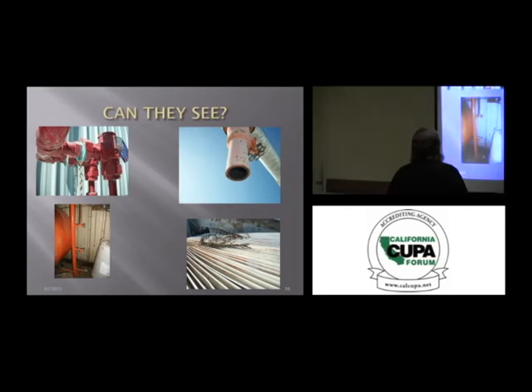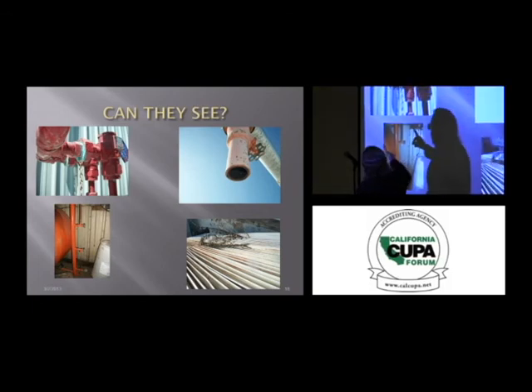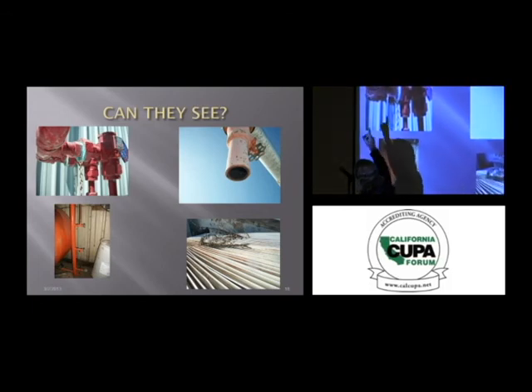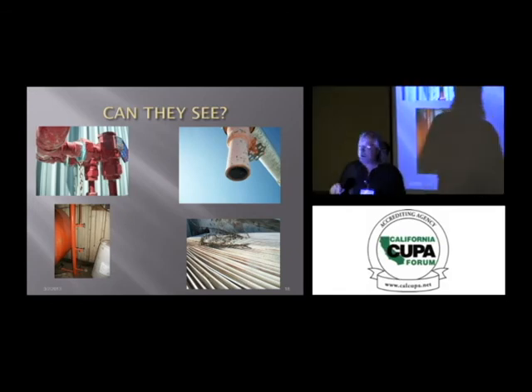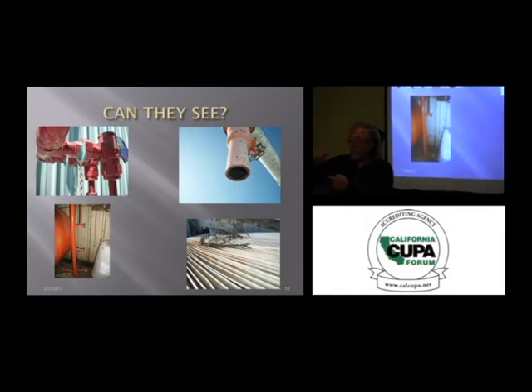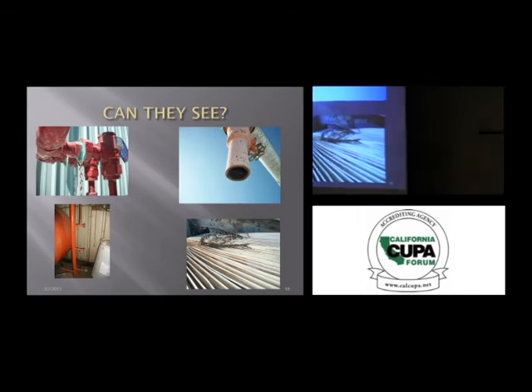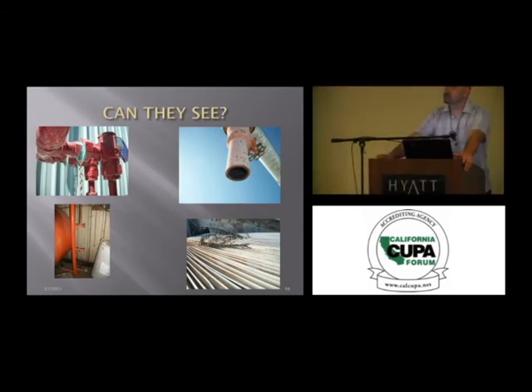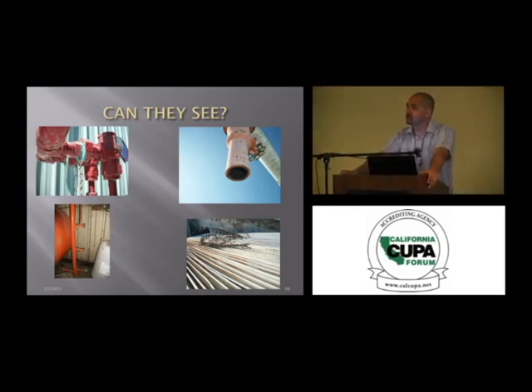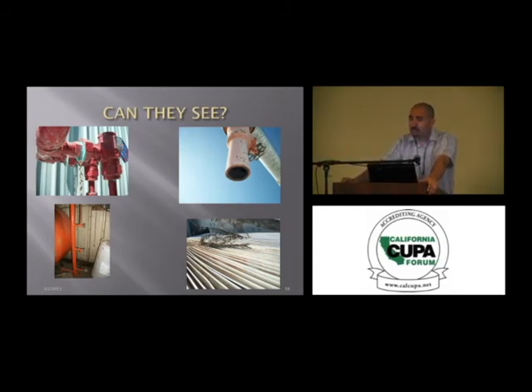What we like to do when we install relief valves is we like to put a little drop leg here, okay? Kind of like what you would put on your gas line to your furnace, so you can catch all the crap down in the bottom, etc. Also, if we have a little bit of moisture that gets in it, it'll get down in that little drop. It won't sit on the relief valves themselves. Yep. Very good.